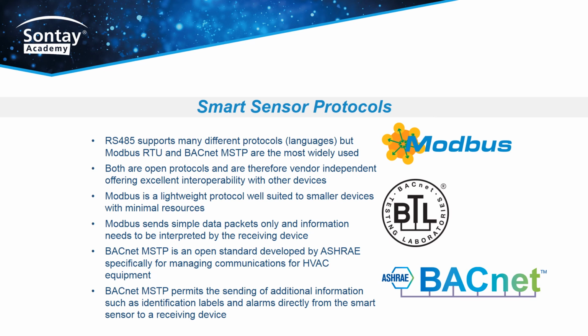Both are open standards. That is to say that anyone can implement the protocol on their device without the need to purchase a license to do so. BACnet, however, does have an accreditation scheme where a vendor can get their device tested for compliance with the BACnet standard in order for it to bear the BTL mark. It should be noted that it is not a requirement of the BACnet standard for a product to be BTL marked, and there are many non-BTL marked devices which fully comply with the BACnet standard.